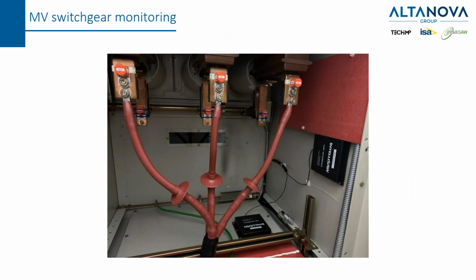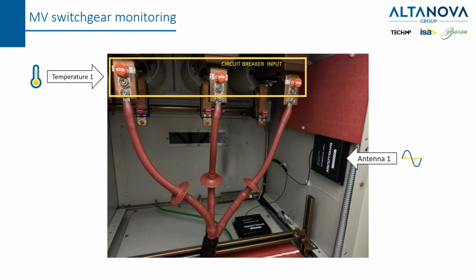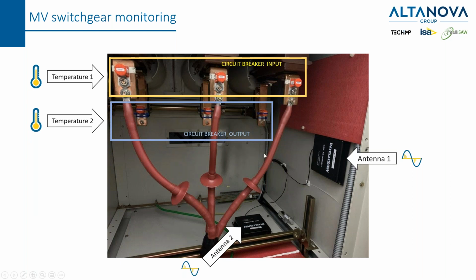In this picture, there is a real example of installation of the system. You can see here the circuit breaker input, and here are installed the hotspot sensors, wireless, as I said, and these sensors are communicating with this antenna interface. On the circuit breaker output, there are 3 other wireless sensors that are connected to antenna number 2 on the bottom side. And here there is the humidity sensor. Everything is connected.